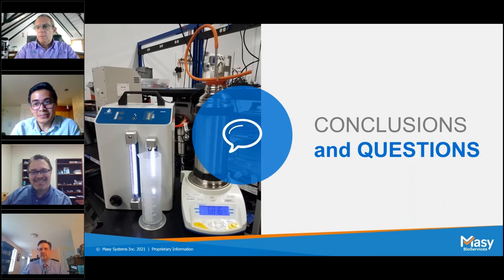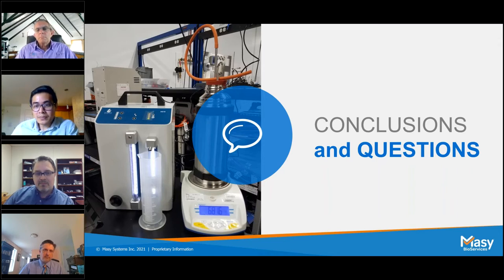The short answer is yes, all of those. Depending on the results of your initial testing in your cycle development, on seeing how well your load items equilibrate, you would look at adding pulses or increasing the depth of the vacuum in the initial pulses to remove as much air as possible. In general, for most cycles, I can usually get away with about 4 negative pulses. But I have seen autoclaves with difficult to sterilize load items. I've seen some that have had up to 6 negative pulses and 7 or 8 positive pulses just to get everything preconditioned and guarantee that you meet that equilibration.